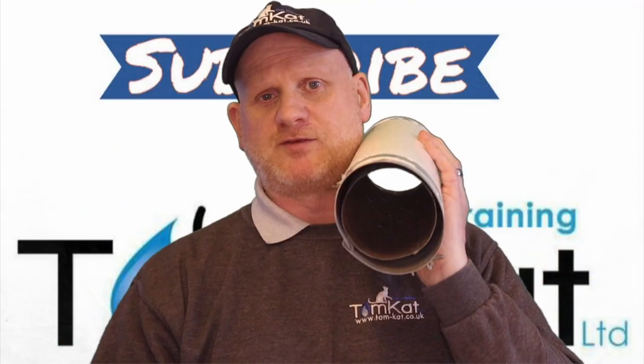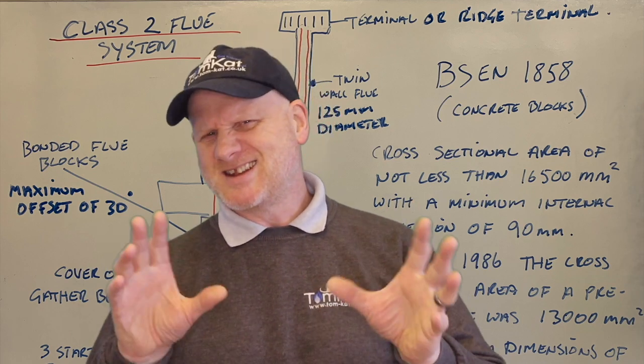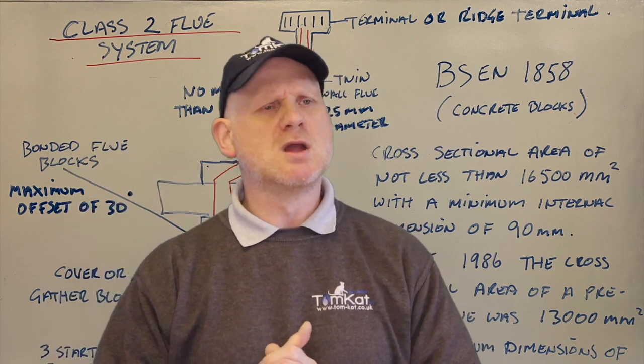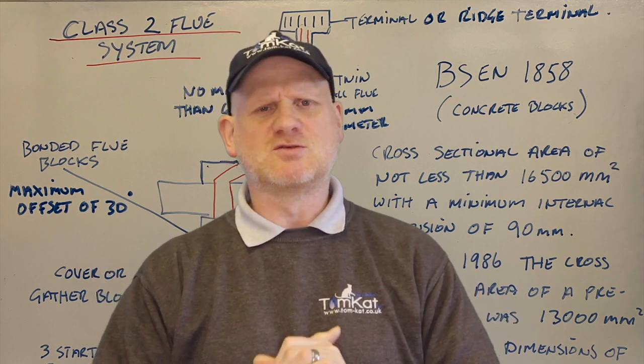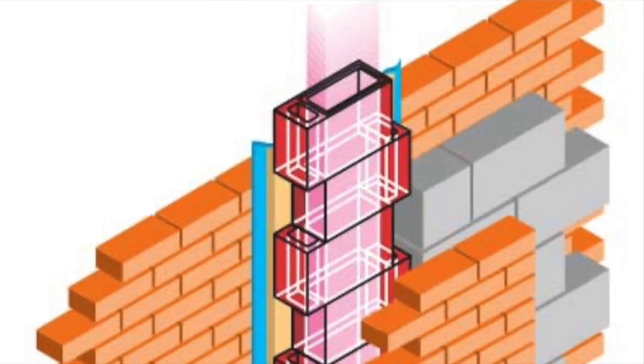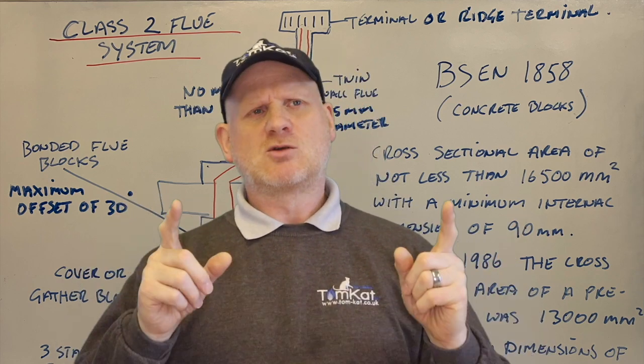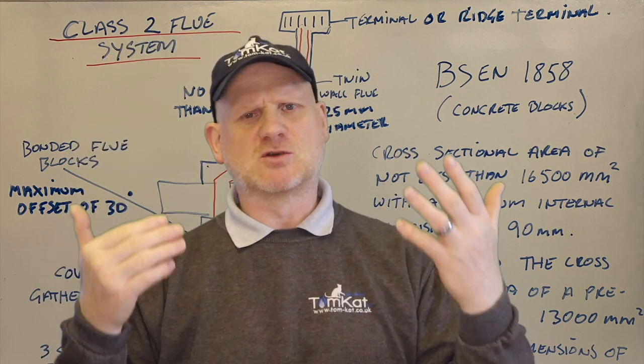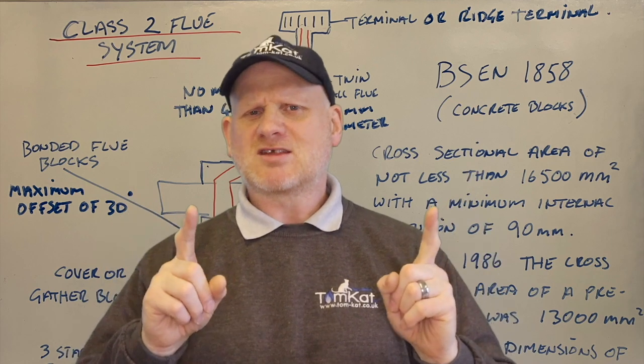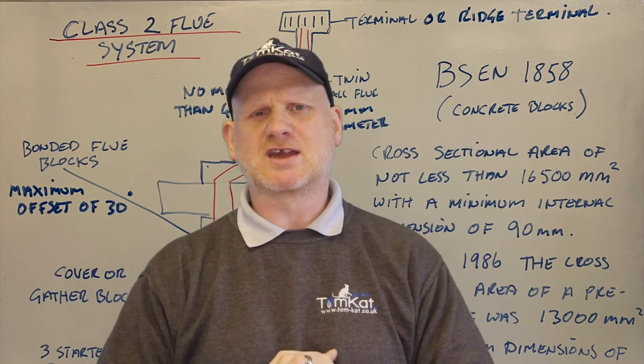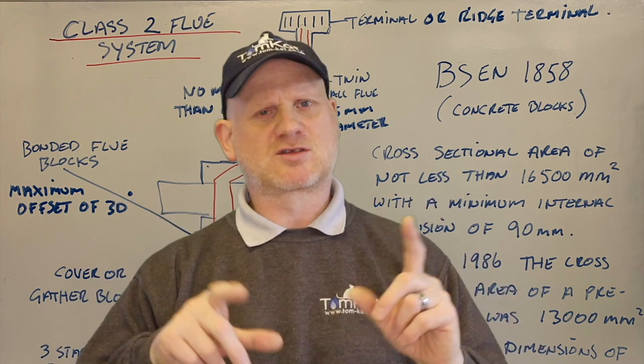Let's switch from twin wall to a precast flue system. In the late 1960s and early 1970s during a house-building boom, instead of building class one brick chimneys, they decided to do class two chimneys — precast flues. A precast flue system is a load of concrete blocks put on top of each other, built into the wall and going up to the loft. Because it was bonded into the cavity of the wall, it gave a flat finish. The plaster finish had to be dot and dab — if you used roughing and finished plaster, it would crack and lift the blocks.